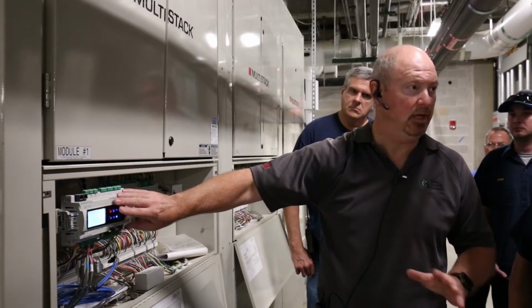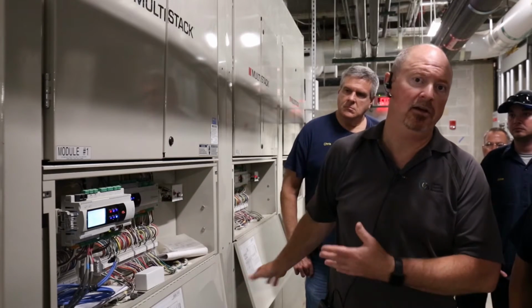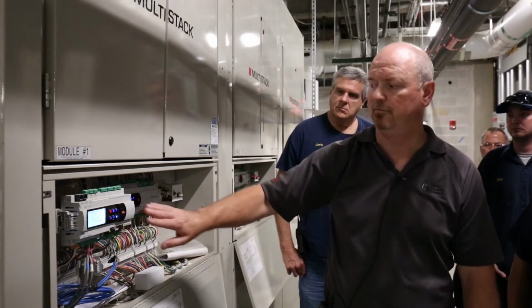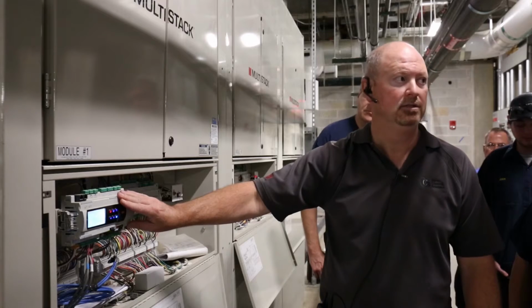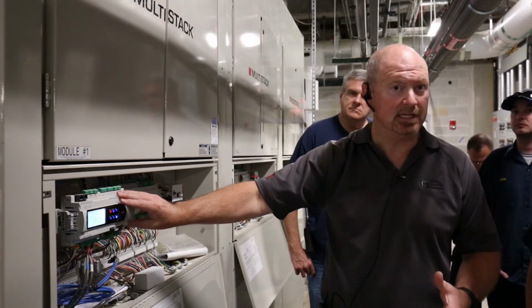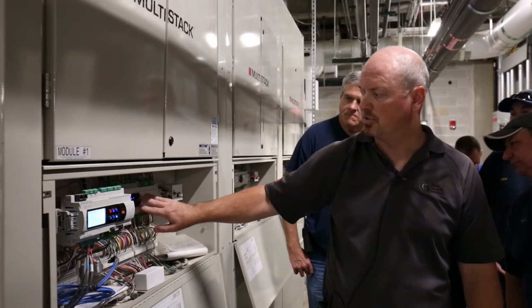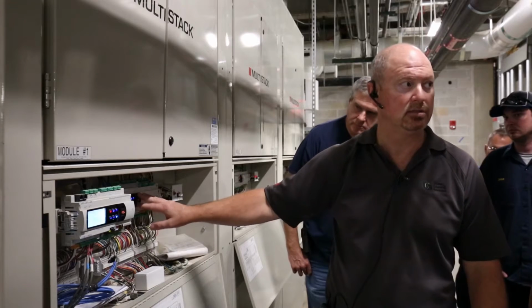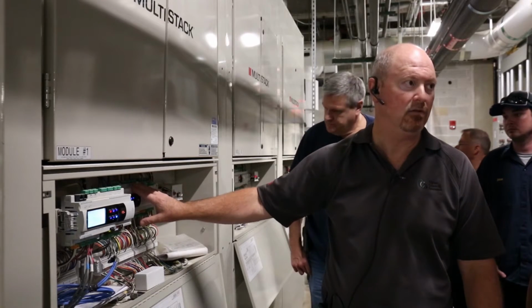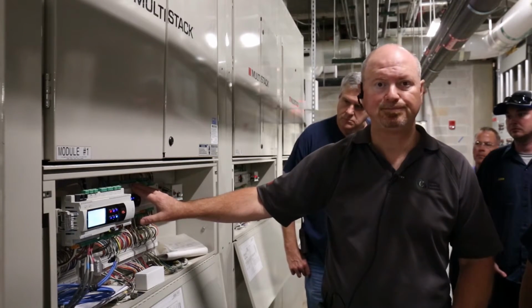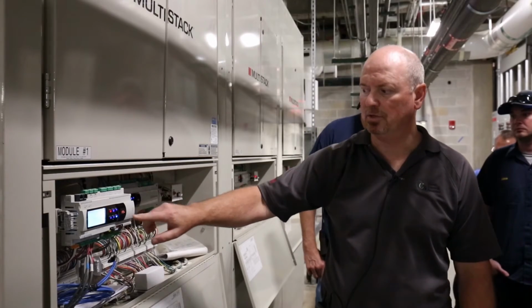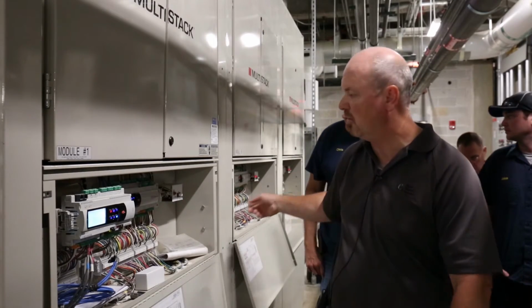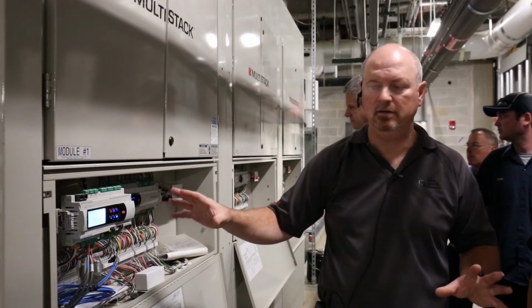Other things in the master, you can see everything on any module in here. You can see it from this controller. That's not the easiest way to see it. You can come over to these controllers and see just as much on the module itself a lot quicker. If you know which module it is, you can just open up that door and go on down through and reset it.